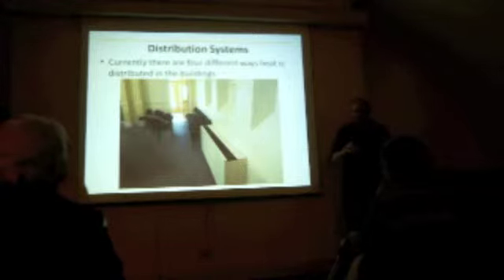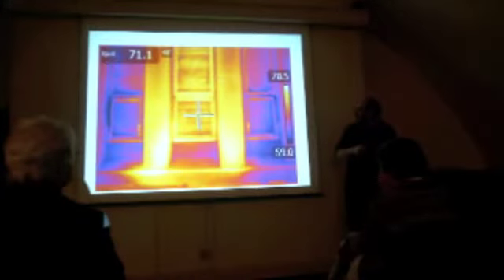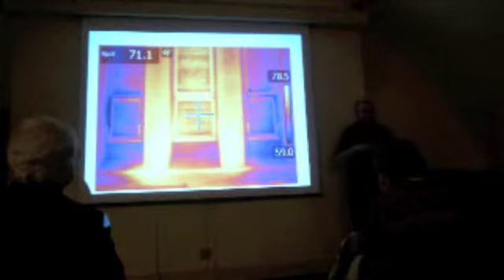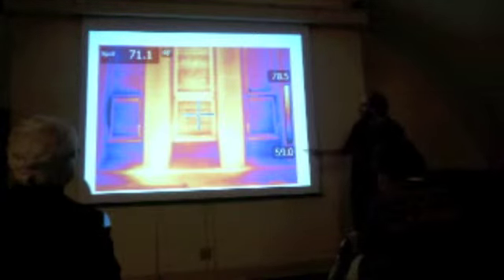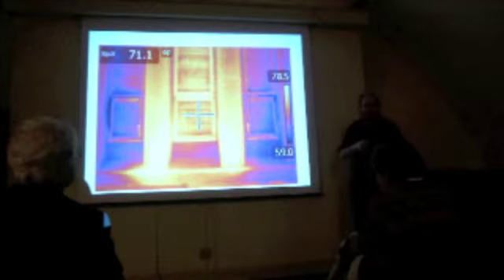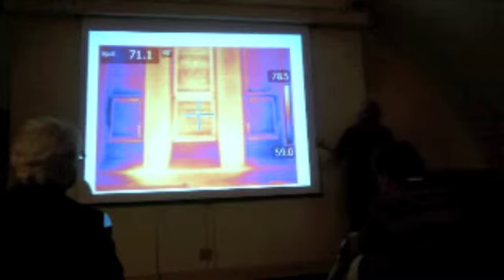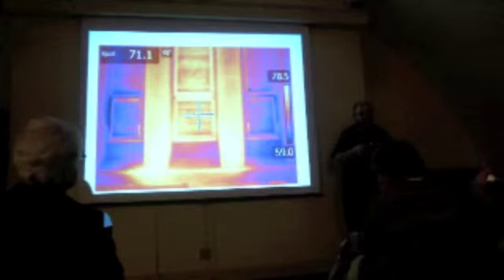And one of the things that we'll see is where and how you distribute the heat will make a big difference in how much you use. Many of these are all along walls, and you can see that this heater is directly underneath those three stained glass windows. This is an infrared picture of those three stained glass windows. What you can see is that the window directly above the hot air blower for the heating system is getting quite a bit of heat. This is a concern because glass is a very poor insulator, and so a lot of this heat that you're blowing up is actually leaking out through that window rather than going into your space.